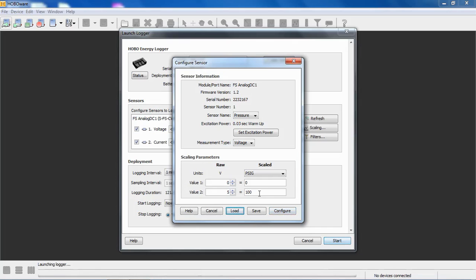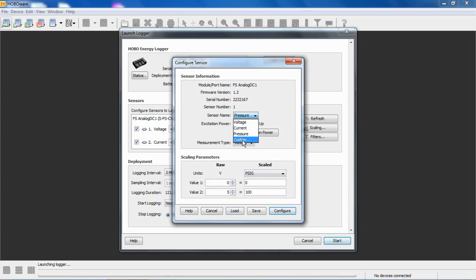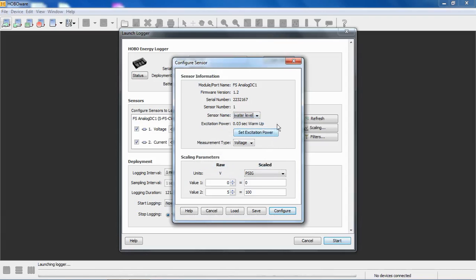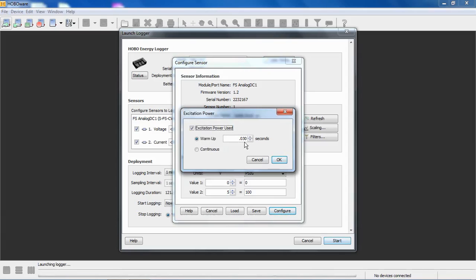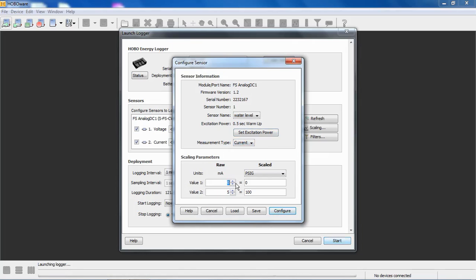If we want to put in a custom configuration, in other words, if we're using this on some other third-party sensor, let's say we want to use it on a sensor that monitors water level based on pressure. So we're going to create a sensor name using our custom configuration, and we want to call this water level. Again, this isn't an outdoor data logger. This is strictly for an example, but some people use water level sensors indoors for water treatment plants and things like that. So click on OK, and this particular device needs a half a second warm-up time based on what the manufacturer said. So we're going to configure it for a half a second warm-up time. This device outputs a 4 to 20 milliamp signal, so we're going to select current as its measurement type.